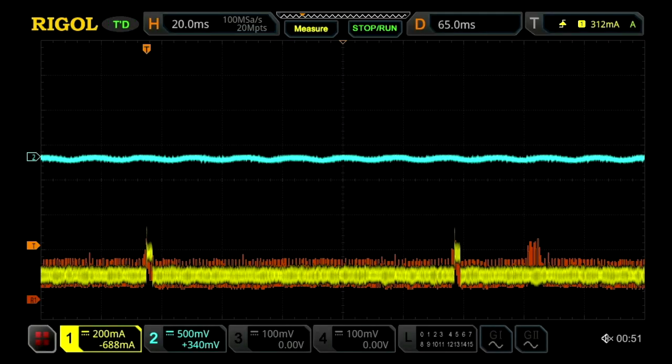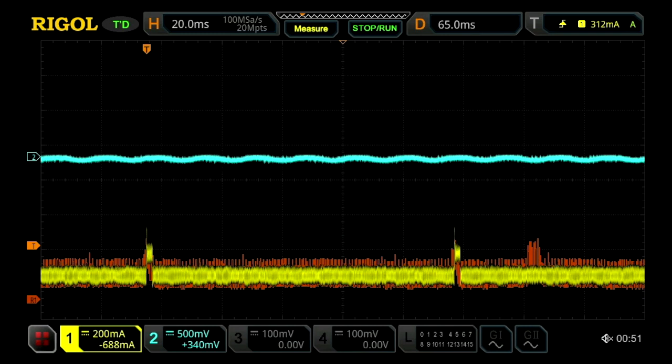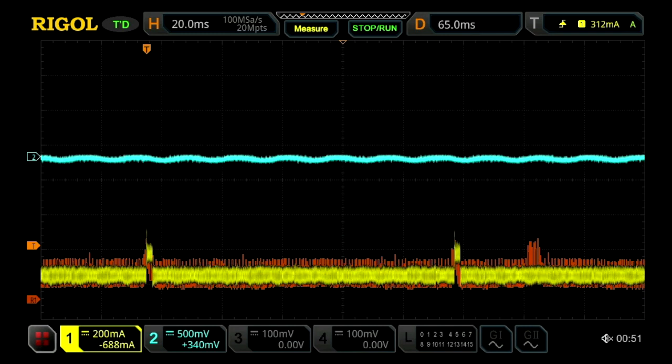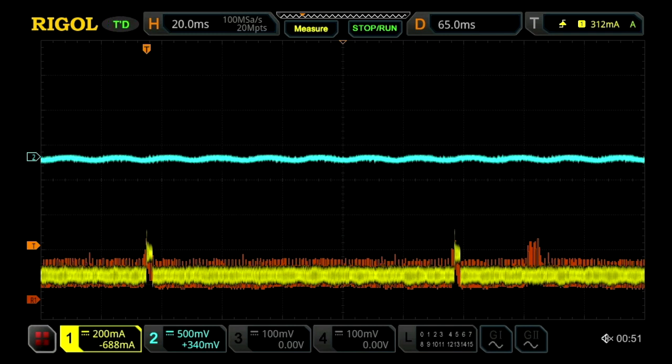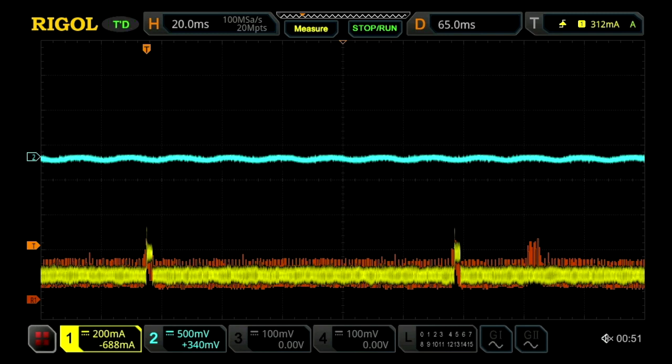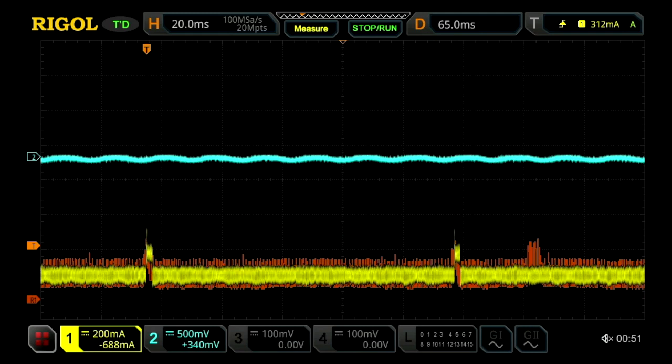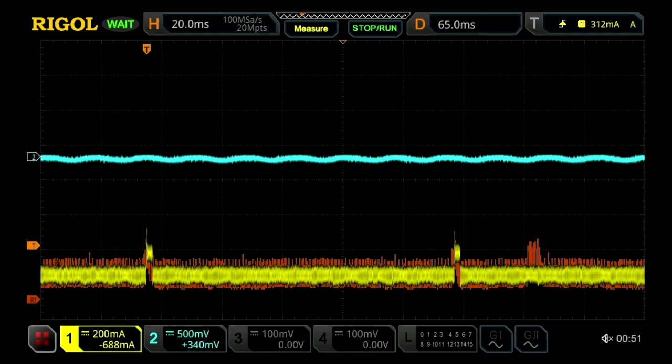I've gone ahead and connected my battery to our electronic load. And we can see here I've been able to recreate the same nominal power draw with our electronic load, which allows us to perform extensive battery testing on just the nominal power aspect of our robot. This allows us to test how long the battery will last when the robot's operating in just a nominal power.